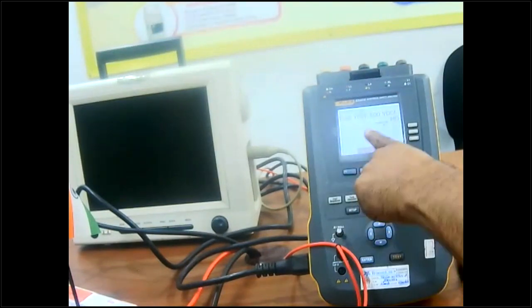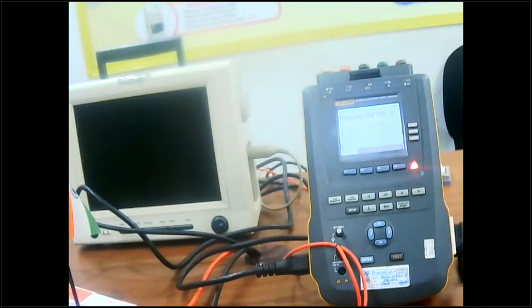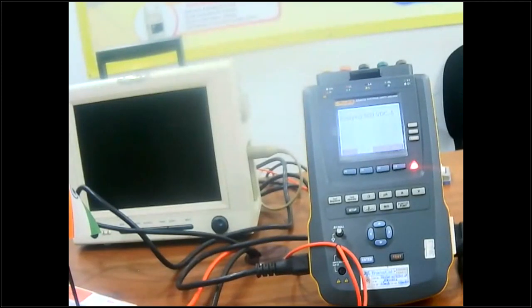Now I am going to test it on the neutral. This is fine. And applied parts to neutral. It's acceptable. These are all the tests we have to do, and that's all for electrical safety testing of the monitor.